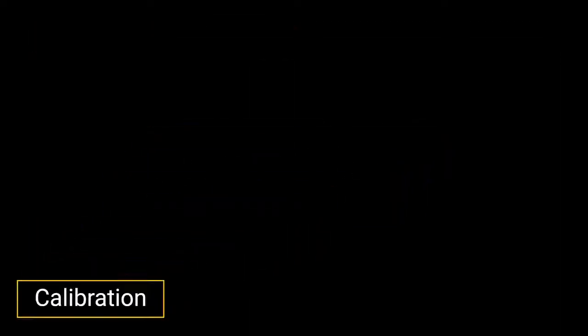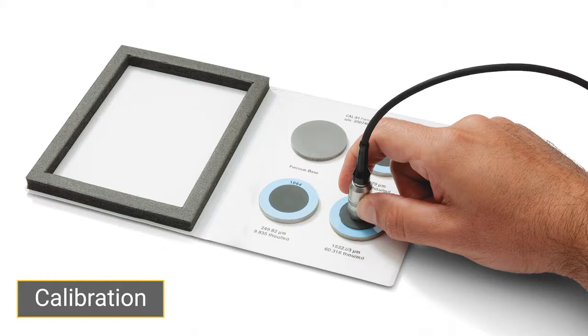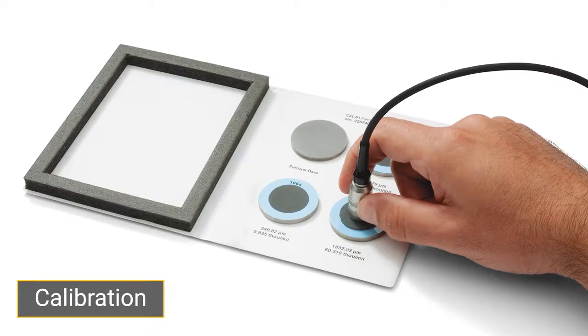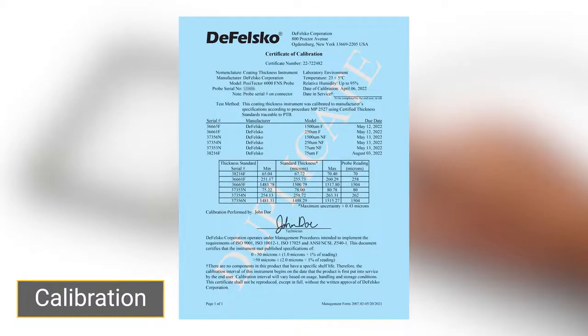Step 1: Calibration. Calibration is performed by DeFelsko or an accredited laboratory and involves taking measurements on traceable standards throughout the range of the probe under controlled conditions. The result is a long form certificate of calibration which is included at no charge with every PosiTector 6000.